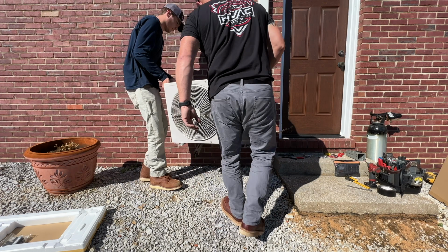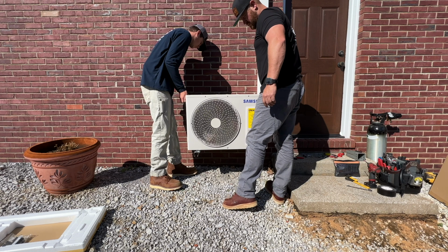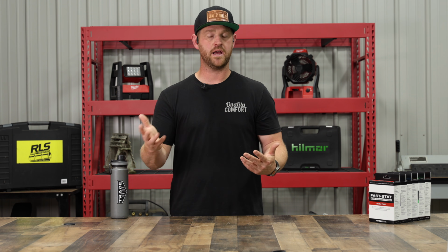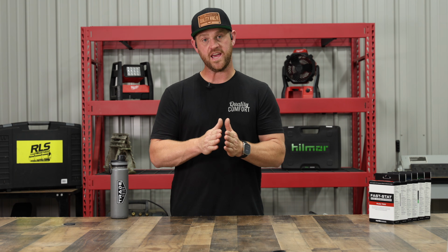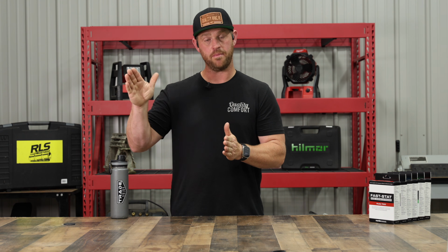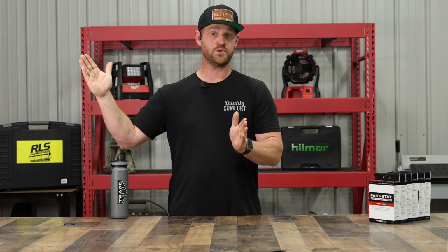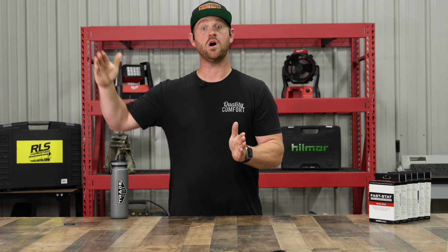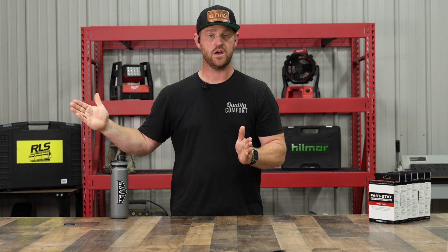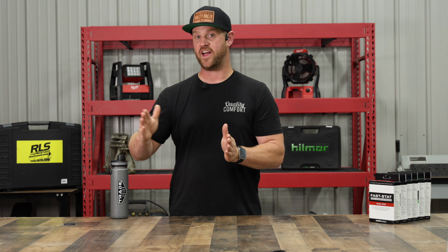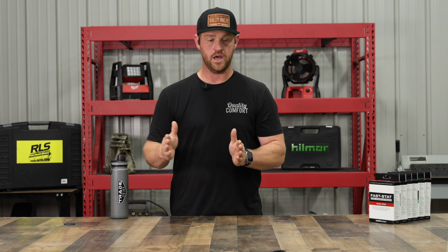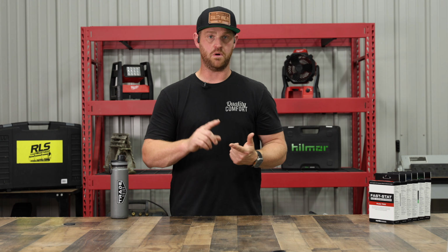And then with variable speed, you get the full spectrum. It has a full inverter, so it can start off at, let's say, 15%. Again, some manufacturers are different, but it can modulate and step up from 15 all the way up to 100%. Some of them can even go beyond 100% and go into overdrive. So you have a lot of flexibility on the equipment side to be able to modulate.